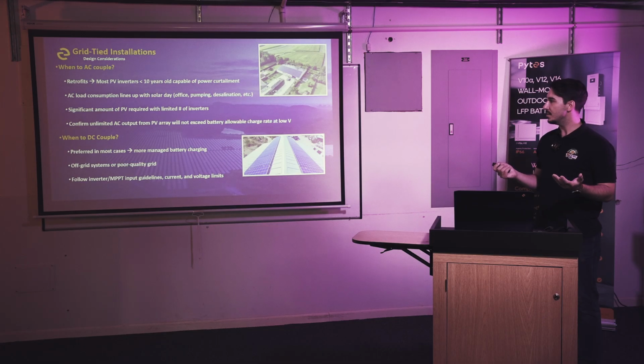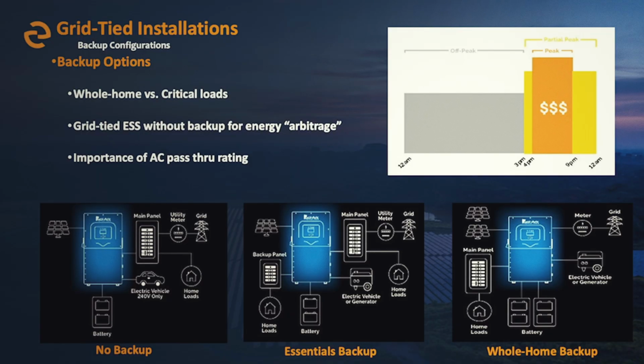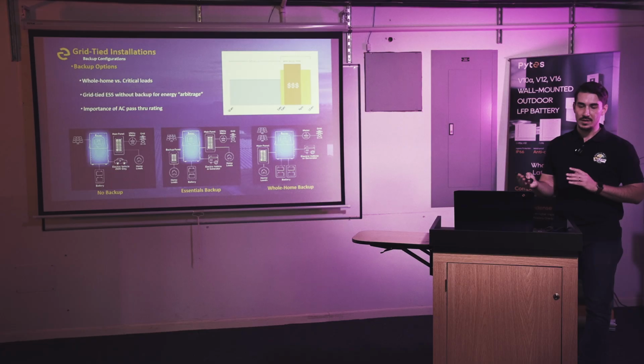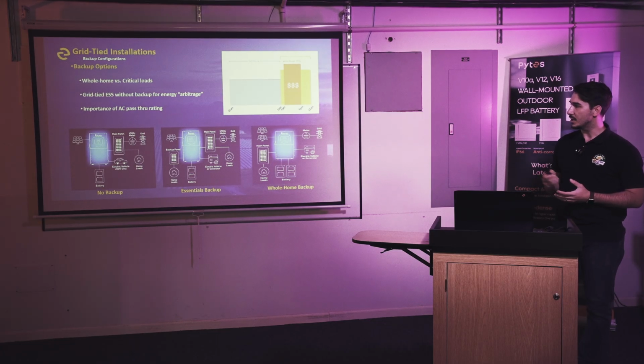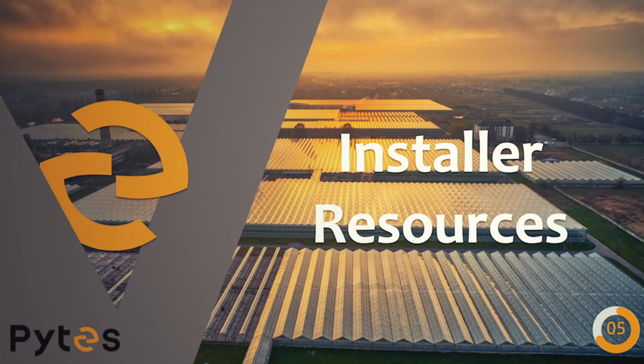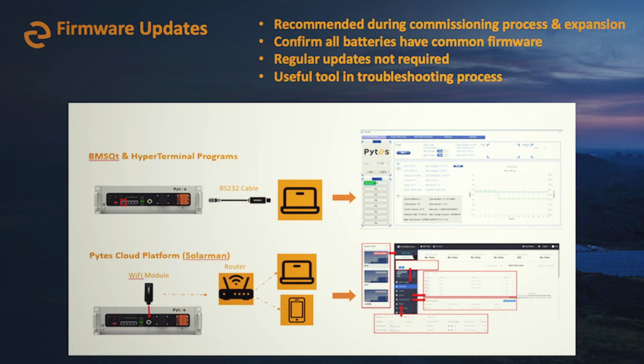When to DC couple: if you're off grid primarily, and generally just for better managed battery charging. You also got to think about your backup options. If it's grid connected, they want battery backup. Are we doing whole home versus critical loads? Do they even need backup, right? Some systems now, especially in California, where they implemented NEM 3, it doesn't make sense to sell your PV back during the day. Maybe they just want to buy and sell energy from the grid at different times and do that energy arbitrage type scenario. But also think about your AC pass-through rating on the Sol-Ark. I know the 15K is a 200 amp rated pass-through, so that's a really good option for whole home backup. And yeah, I'll skip through most of this.